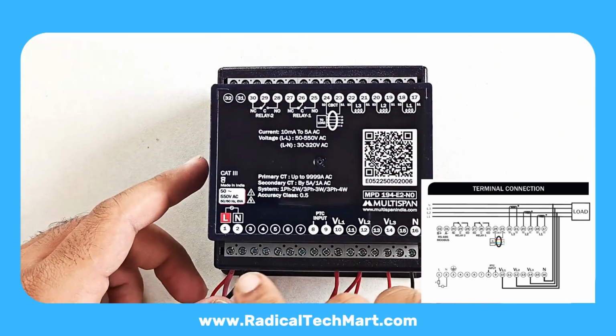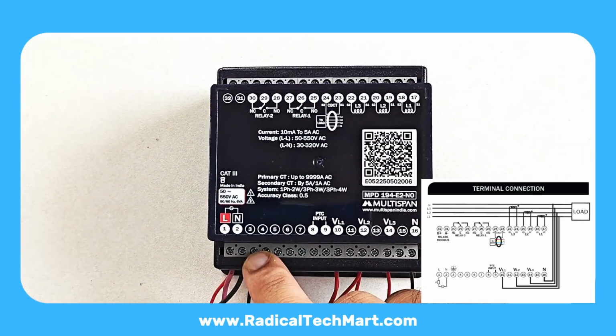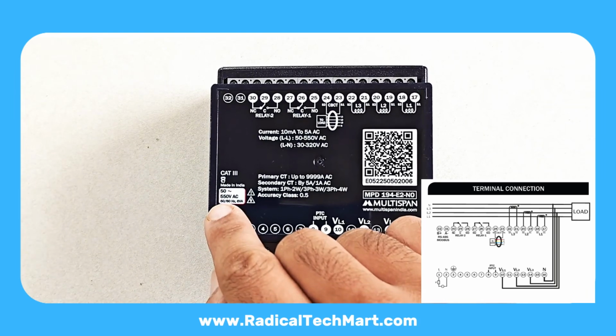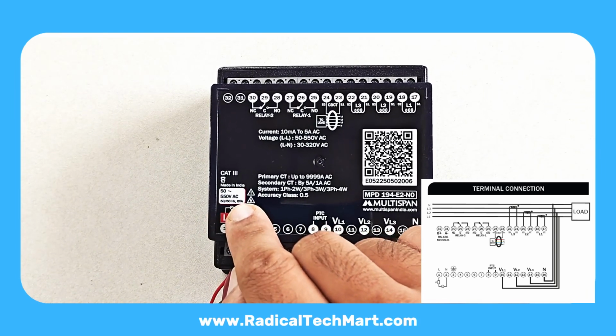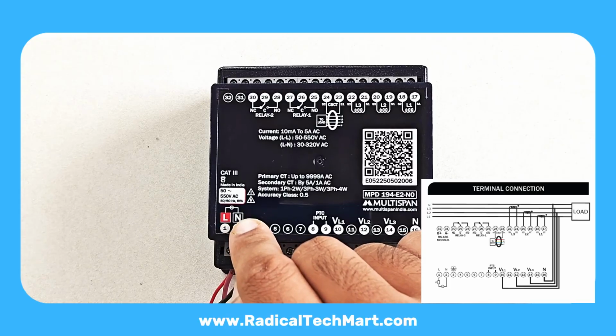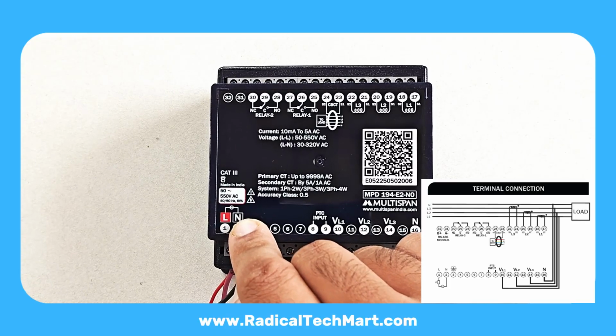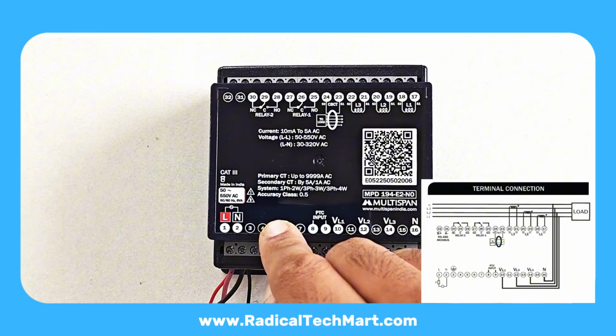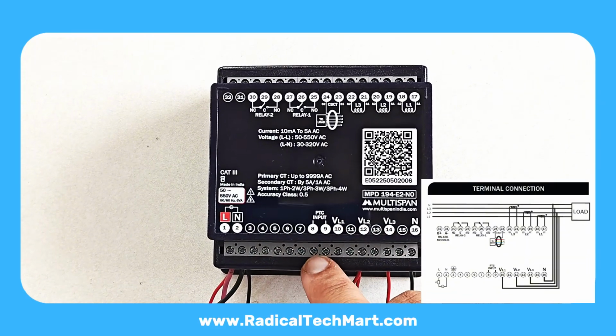Inputs and overview. Let's first understand the inputs and terminals. Terminals 1 and 2, auxiliary supply, line and neutral. Supply range, 50 to 550 volt AC. Any auxiliary supply within this range can power the instrument.